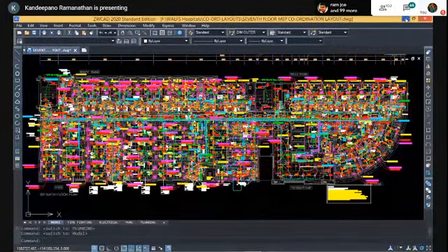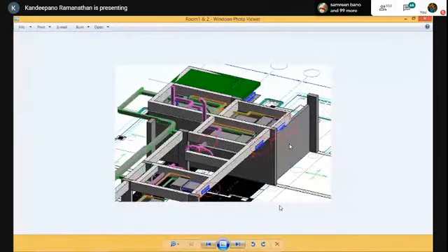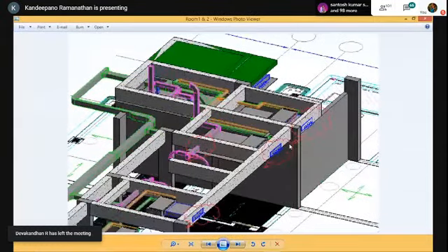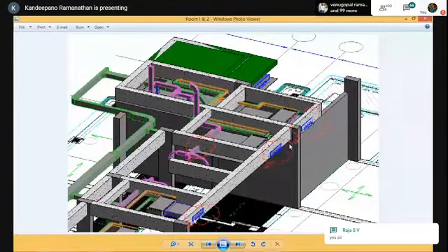So for example, for this only nowadays drawing tools have come, Revit drawings. I have Revit open, with which 3D views are possible. If you look up here, there is a concrete beam, right? There is an air conditioning equipment behind this. People can see what is on the screen. Yes, sir. This air conditioning equipment, this is the fan coil inside. This is small duct length where the air comes out. This is the air grill. Now this is obstructed by a concrete beam.